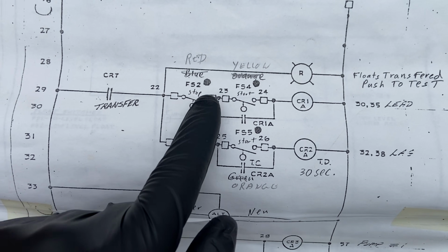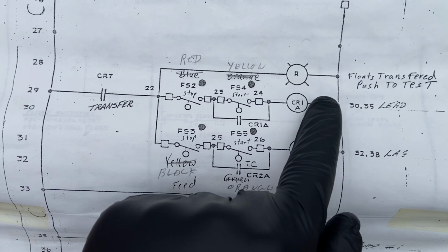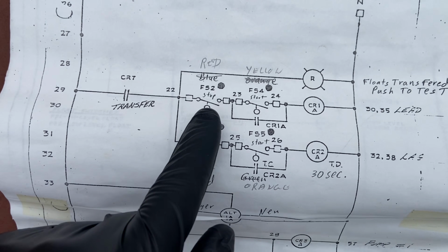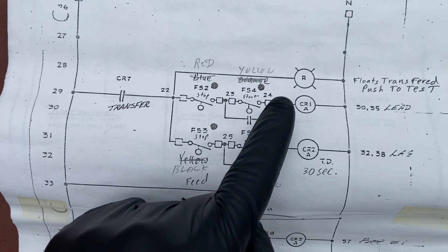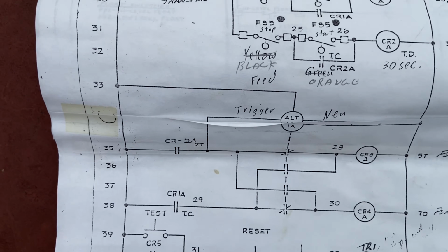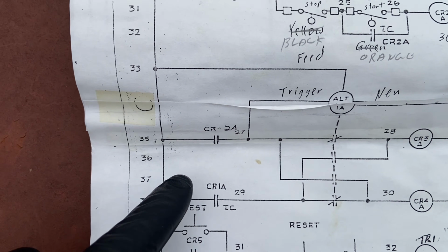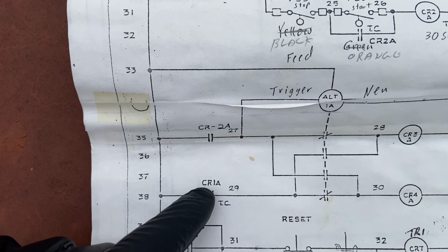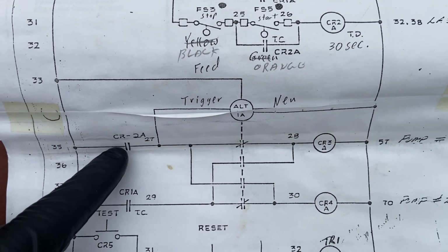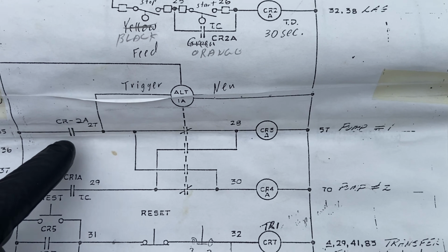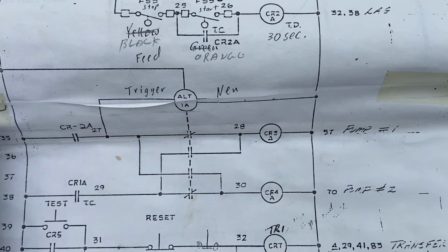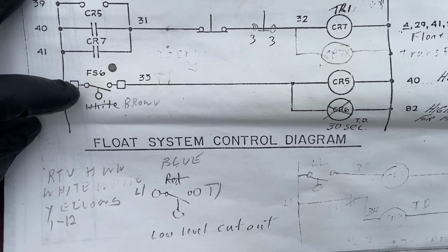Goes to these relay CR1A and CR2A. And those are latching circuits where the relay latches itself in around the start float to give you a pumping range and doesn't stop until the stop float drops out. And then there's contacts from those relays going to this alternating relay, which decides which pump is lead and which pump is lag and alternates each time the lead system stops.